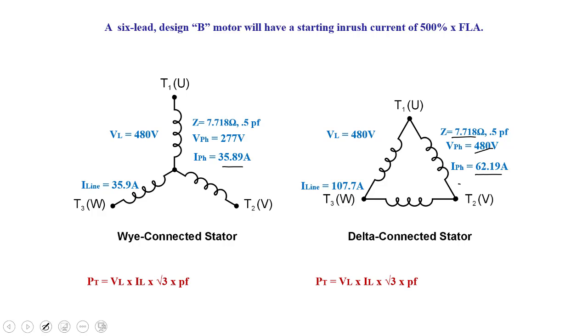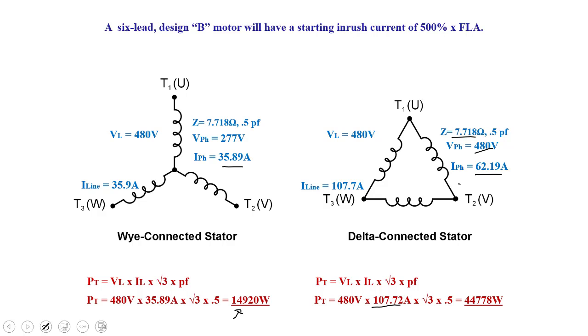Running it through our power formula, V line times I line times √3 times power factor, we're going to produce about 14,920 watts in Y. The true power when we connect it in delta, 480 times 107.72 times √3 times 0.5, is going to be 44,778 watts. So we see 3 times more power.